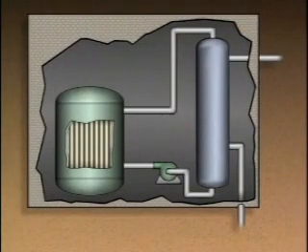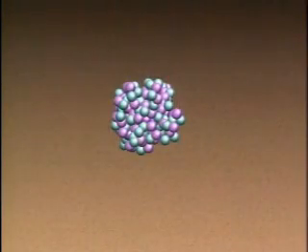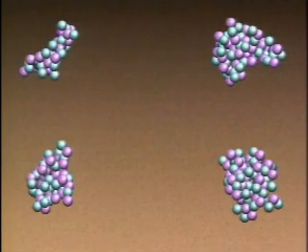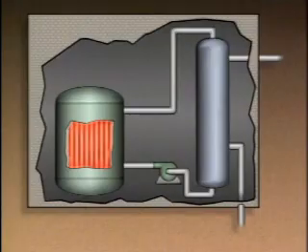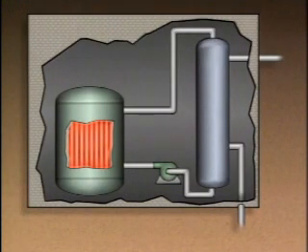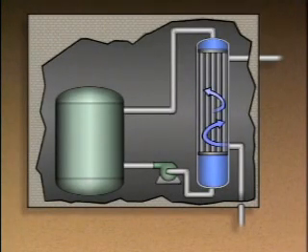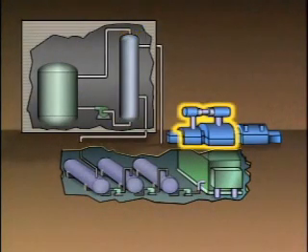The reactor contains the fuel that the plant uses — in most cases, uranium. When the plant is operating, the uranium breaks down in a process called nuclear fission. The breakdown of uranium produces fission byproducts, and as the fuel fissions it produces energy that is converted into heat. This heat is transferred to water flowing through the reactor, which is kept under high pressure so it will not boil inside the reactor. When lower-pressure water receives the heat, it boils and changes into steam. The steam produced in the steam generator is then directed to the turbine.